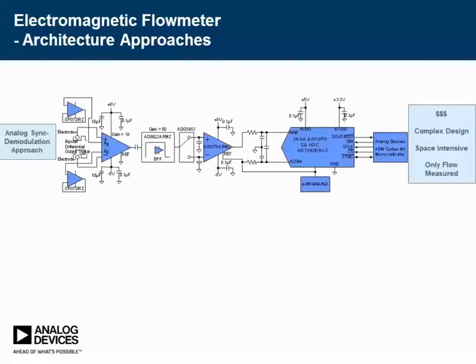Although the specific implementation could be very different from one manufacturer to another, the sensor signal conditioning circuitry for the electromagnetic flow meter can be classified into two major categories: the analog synchronous demodulation architecture and the digital oversampling architecture. The analog demodulation architecture is conventional but still widely used in the industry. It usually has a pre-amplifier, an amplifier with bandpass filter, sample-and-holds, analog-to-digital converter, and microcontroller.